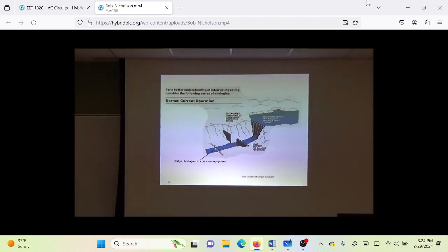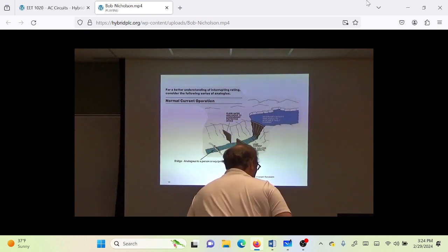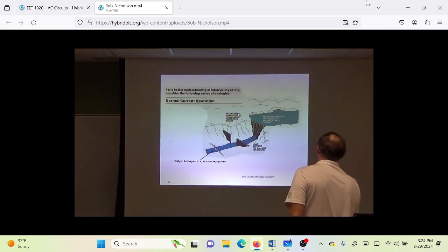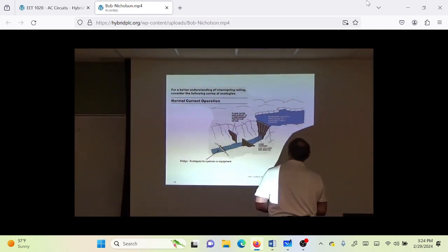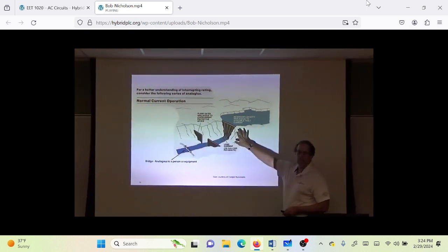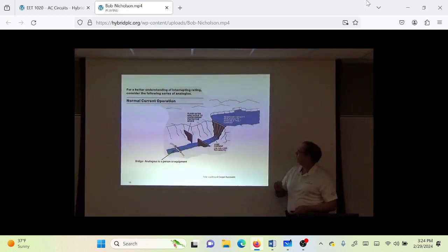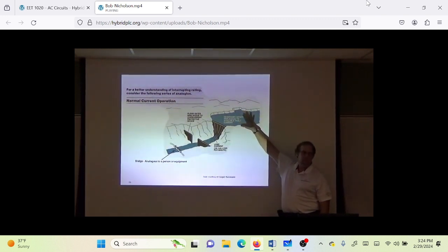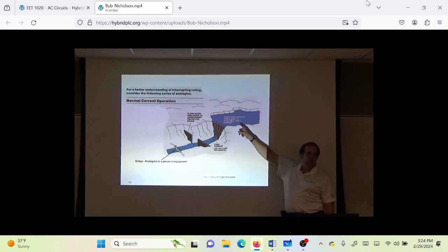Okay, these are the three most important slides to explain this. And you will understand this better than most electrical engineers that have not studied power. I'm going to use water to explain this, so it'll be a very good representation. This lake right here is an enormous volume of water. We're going to call this your transformer. This is the transformer for the building. In that transformer is 50,000 amps, depending on the size of the transformer. That's called short circuit current or fault current. It's in the transformer. It's there, but it's not in the building.